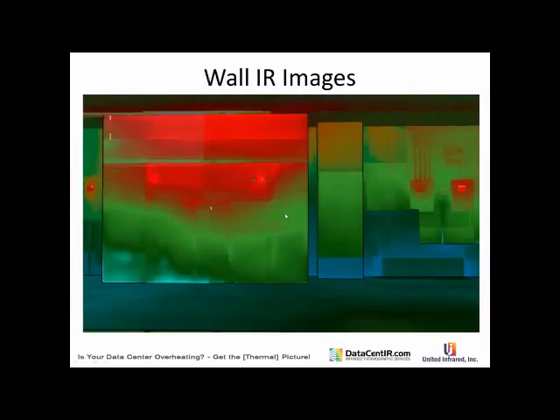This is that one, the Freon's low in this. Also, another reason for shooting the walls is that some of these data centers have outside walls, which is not that bright an idea. But they've got outside walls, and then they've got maybe a metal deck, a couple of inches of insulation, maybe some foam insulation, some TPO that is supposed to be a green roof. It's not that well insulated, and it has a lot of air leakage problems. So knowing what your building's doing thermally is a very important component.